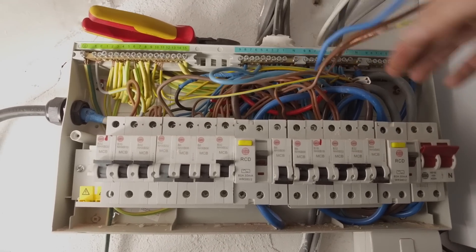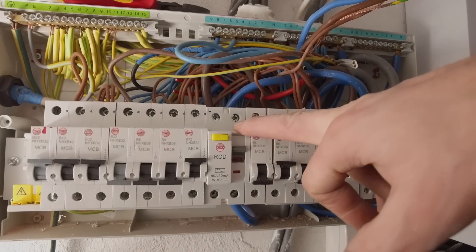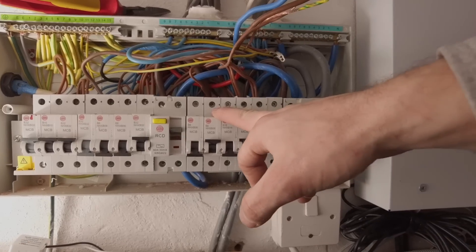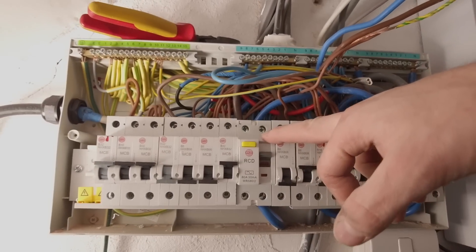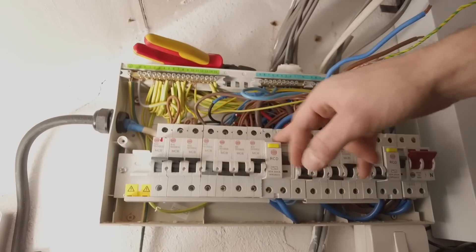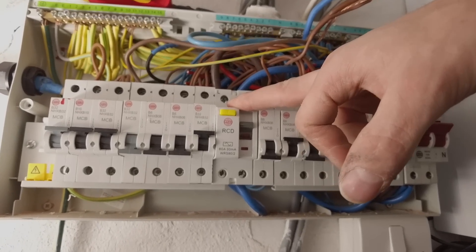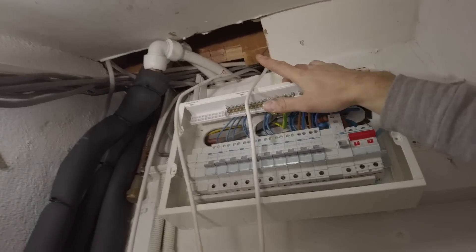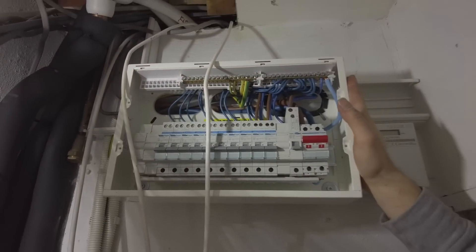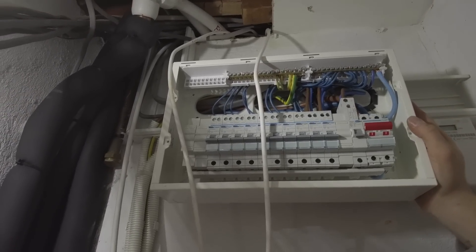Currently what we have here is an old dual RCD fuse board. We can't use type AC RCDs for the solar panels, so what we've done is mount a new fuse board with type A RCBOs. This is a better job because we prefer RCBOs over RCDs — in the event of anything tripping, the RCD controls all the circuits which causes quite a nuisance for customers, so with recommending a new fuse board she was more than happy to change it. We also weren't happy with the location because the cables were coming across the heating pipes, so we relocated the fuse board and redressed the trunking, as the old trunking was in pretty bad condition.